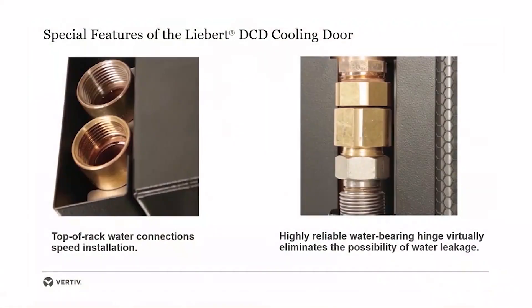So how do you do that? We use DCD doors so that we can get that power in the racks and have the cooling abilities. Some of the products we looked at worked well, but some of them had rubber hoses that swung with the door, or door hinges rather than internal hinges. The durability was a really huge consideration for us.